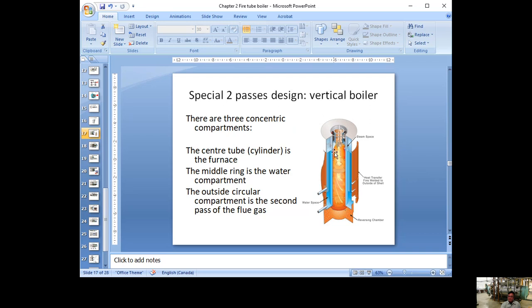So in this vertical tubeless boiler you have one part coming down, then a reverse path, then going to the chimney — two passes. The three concentric compartments: the center is the furnace, the outside annular ring is the return gas path. On the outside they put metal fins — like a radiator — to absorb more heat. In the middle compartment there's water, with a water inlet and outlet.